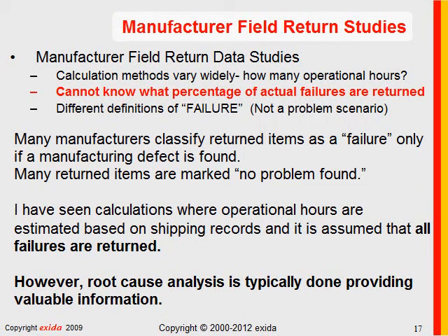Many manufacturers have a process where a returned unit is tested by a technician, perhaps on a bench. And if the technician doesn't find anything wrong, they're marked, no problem found, therefore not a failure. Hey, you're not even close to the operational conditions of the field. Maybe it fails in the field, but doesn't fail on the bench. Those are all things that make this particular data set questionable for calculating absolute failure rates.